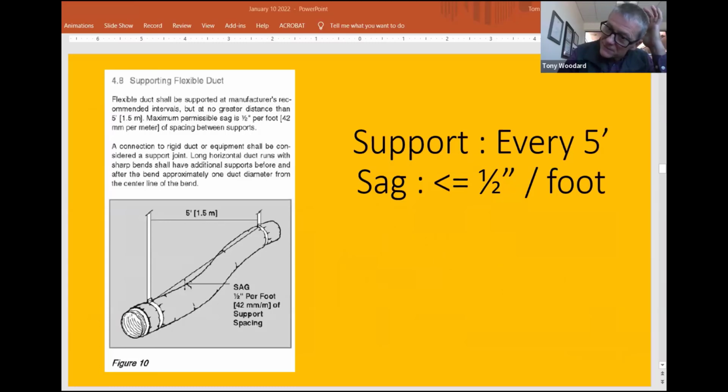Yeah, and that's actually been the latest guidelines of ADC, every 4 foot now. Is that right? Yes, sir. I'm sorry, I'm just thinking about some of the ducts that I've seen. Yeah, right. And they're showing the example of what you get when you go by their CFM chart of what they're wanting to achieve at 4%. That's how much sag they're allowing, half inch right there, if you run that properly.